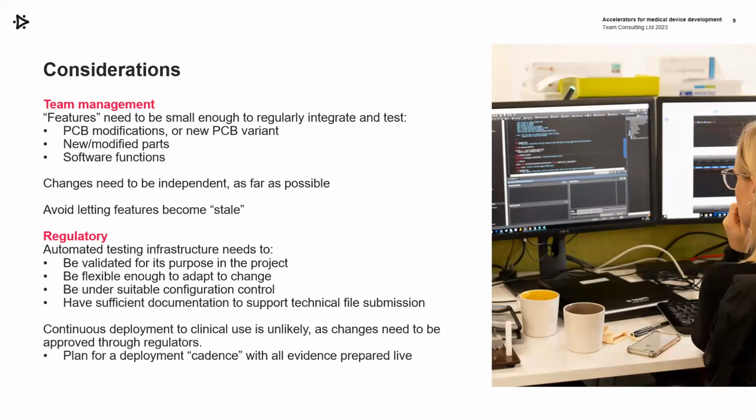As with anything under medical device development, our automated tests need to be under configuration control and need to be managed as though they are as critical as the device we're working on. It's testing our medical device, and if we don't have confidence in the things we're testing and the things that we're using to do the testing, we can't gain confidence in our system. Finally, it needs to have documentation that's suitable for the level of submission that we're performing. Different regulators ask for different things, but they're mostly related.